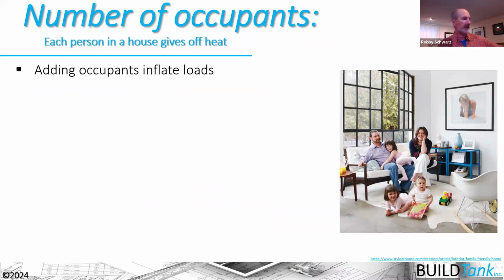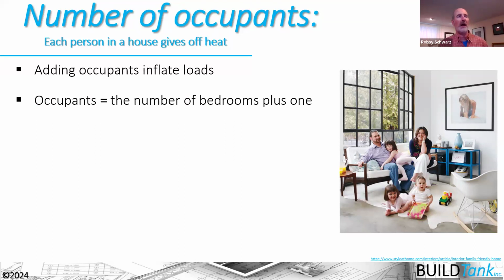Okay, the number of occupants can also impact our loads. We've seen cases where people have added occupants to the house. The occupants are generally described as the number of bedrooms plus one, assuming that in the primary suite we're going to have 2 occupants living in that suite. So that's how we would size a typical house. So if I have a 4-bedroom house, I would want to enter 5 people into that house. The number of bedrooms plus 1 equals the occupants in that house.